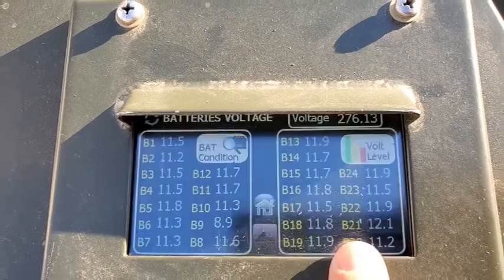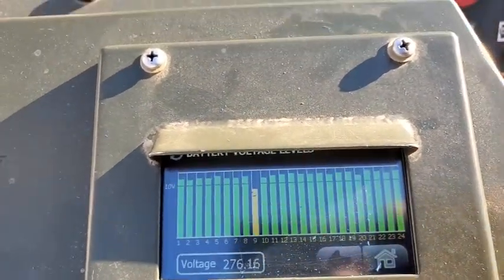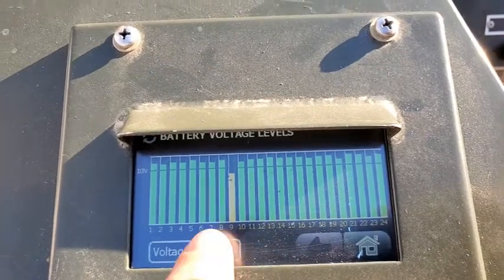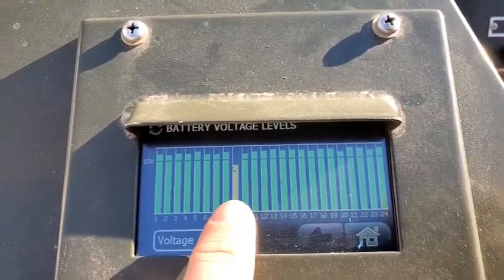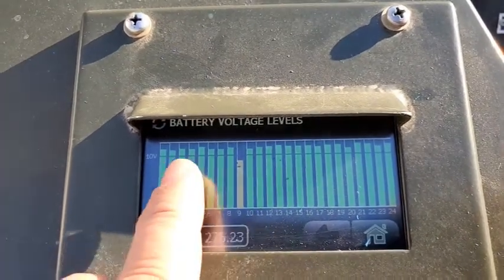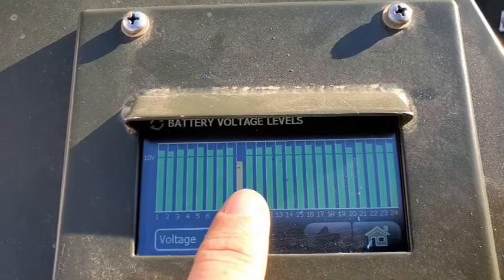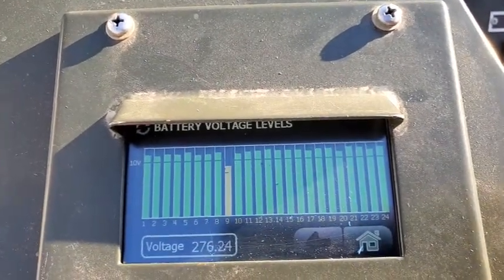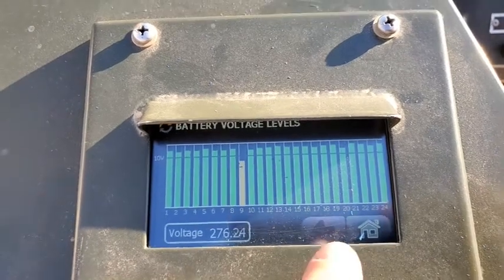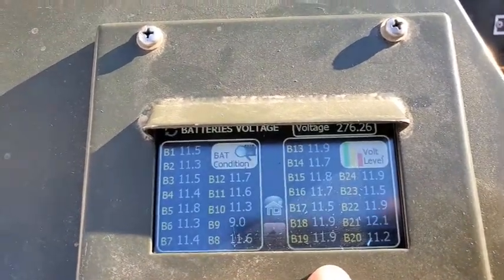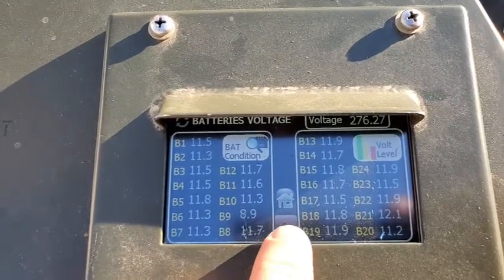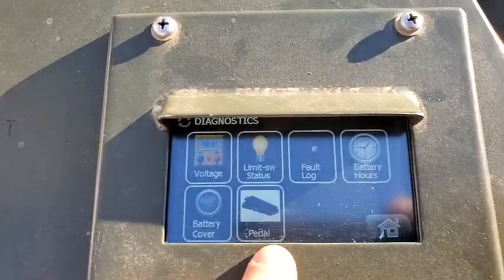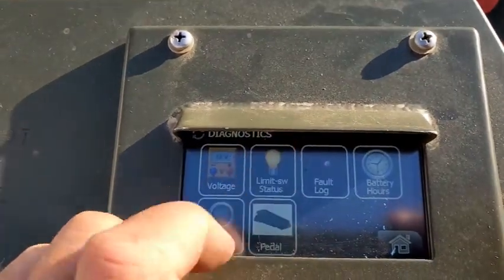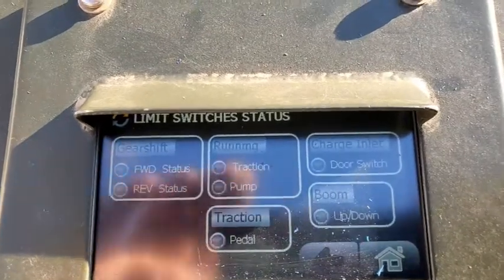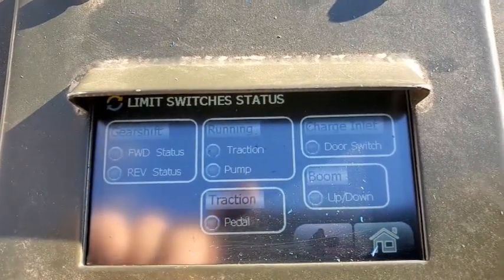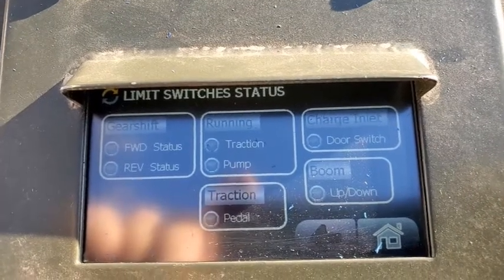We can return and check the voltage level, the waterfall. Alright, so we have one battery here that is quite low. This battery could and will start causing other batteries to start draining into it, leading to a shorter lifespan. Return, return again. Limit switch statuses. When any of these are activated, they will turn green.